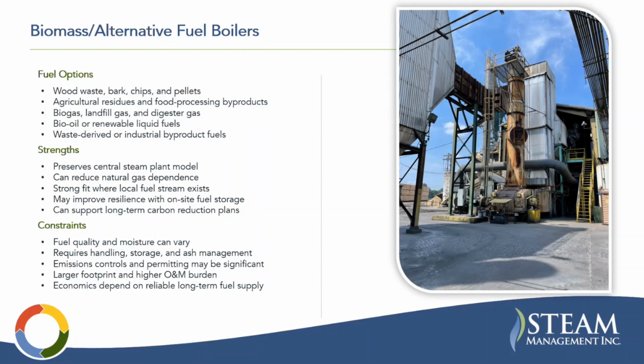Some constraints: the fuel quality and moisture can vary. It requires handling, storage, and ash management. Those are complicated systems with significant electrical loads. Emissions controls and permitting can be significant, and there's a larger footprint and higher O&M burden for these large boilers. Economics depend on reliable long-term fuel supply as well. So, for example, say you're using TDF, tire derived fuel. It's an alternative fuel, maybe not a carbon neutral fuel. Are you going to be able to get that consistently for the next 10 years? So you have to really evaluate where the fuel source is coming from in order to invest in installing a huge tire burning boiler, right?